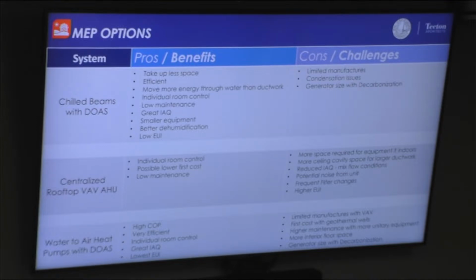Very efficient. You move more energy through pipe than you do through ductwork. What you move through a 1-inch pipe is equivalent to what it takes an 18 by 18 duct. So for cooling with rooftop DOAS, you need an 18 by 18 duct to do the same thing a 1-inch pipe will do for chill beams. So a lot less space being utilized to do what you need.